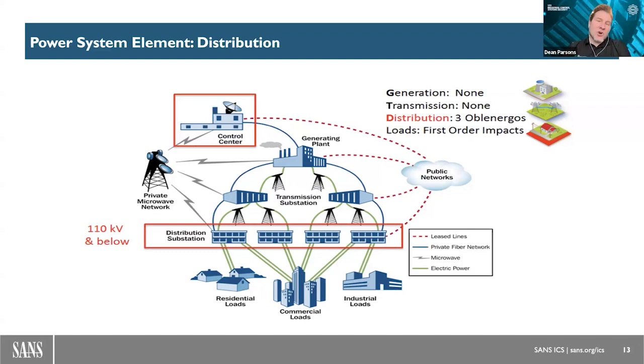As a result of this targeted attack on the electric facilities at the distribution level, the adversary went onto those HMIs and literally clicked on disconnect breakers in many cases. Now that's oversimplifying, but generally that's the idea. So the adversary focused on getting access like an operator would, and used that power and authority against the control system.